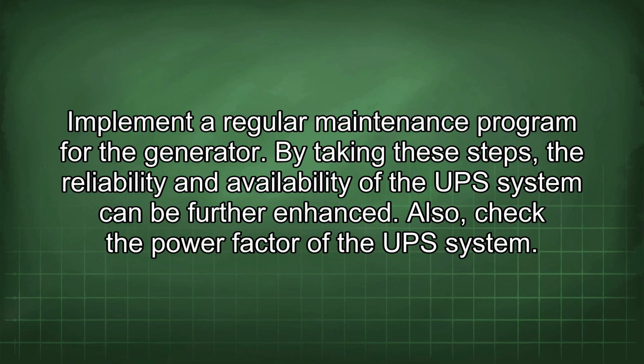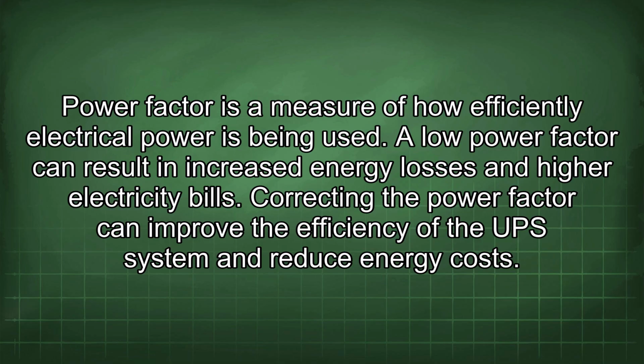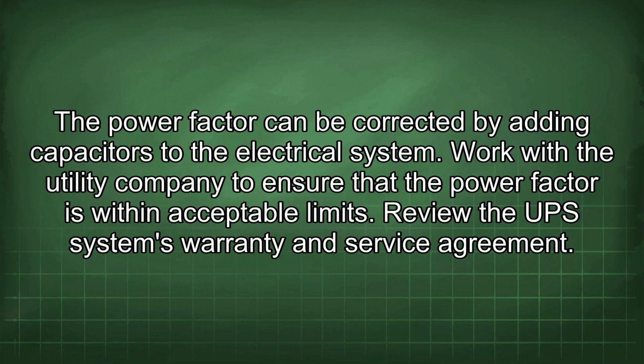Also, check the power factor of the UPS system. Power factor is a measure of how efficiently electrical power is being used. A low power factor can result in increased energy losses and higher electricity bills. Correcting the power factor can improve the efficiency of the UPS system and reduce energy costs. The power factor can be corrected by adding capacitors to the electrical system. Work with the utility company to ensure that the power factor is within acceptable limits.